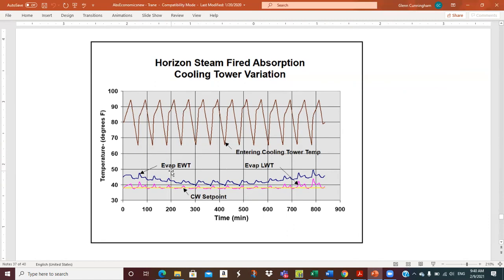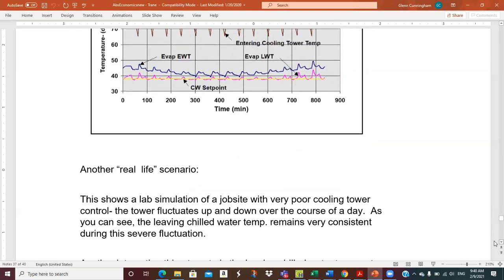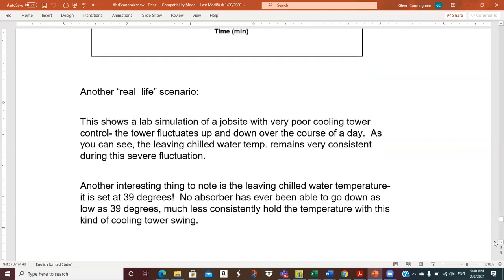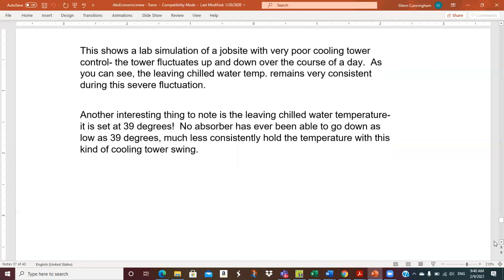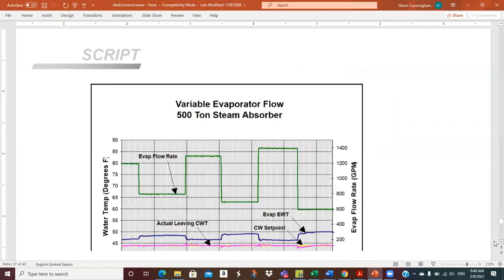And so we can see the evaporator. So this is the chill water coming back, entering water temperature. And then this is the leaving water temperature, which really, you know, is fairly well controlled. You see a little blip. And of course, the set point stays constant throughout. Oh yeah, the other point they make here, this set point is 39 degrees. Well, back in the old days, there's no way. I think 42 used to be the lowest that you could get out of an absorber. And so now with the better controls, we're able to get 39 degrees, which is actually pretty impressive from an absorption machine. Let's see what else they're talking about here. There's the fluctuation. There's the 39. I guess that's all on that one.